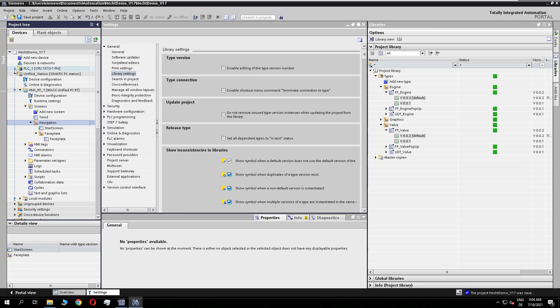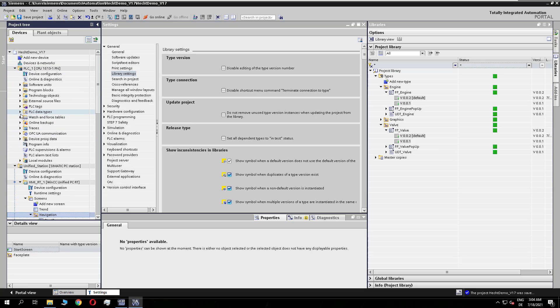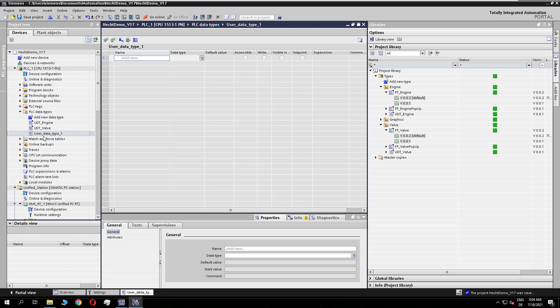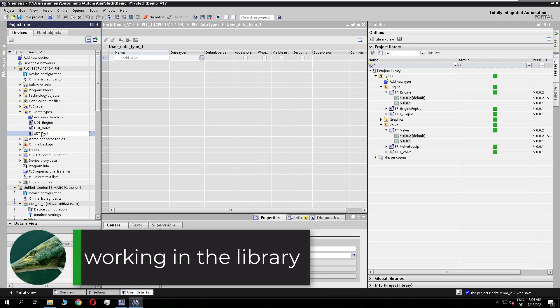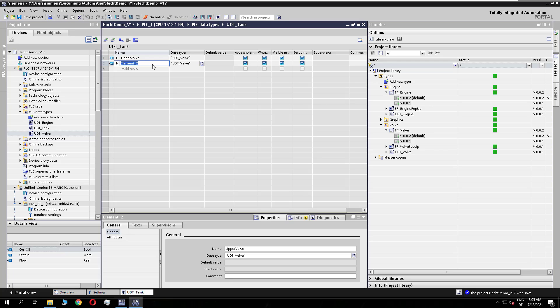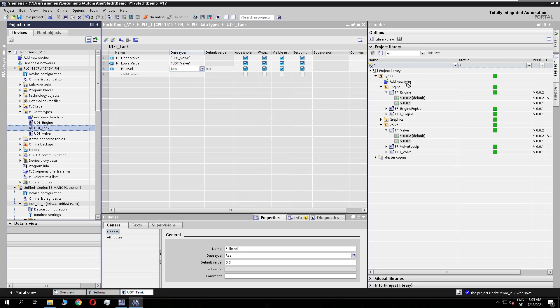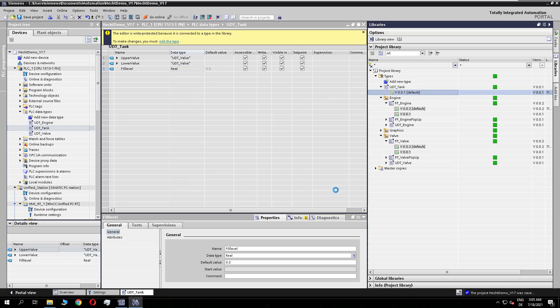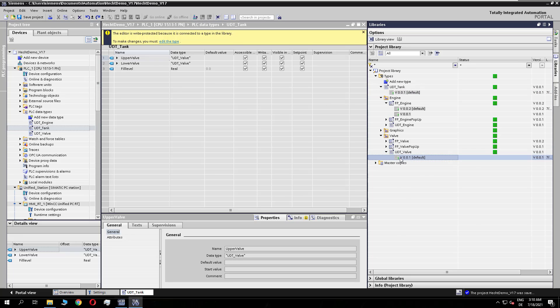To show how to deal with the new library concept, I first create a new data type called 'UDT tank'. This UDT includes two instances of 'valve' — the first one is the upper valve, the second is the lower valve — and I add an additional value for the fill level. I then put this new UDT into the types. It shows green, so that's fine.